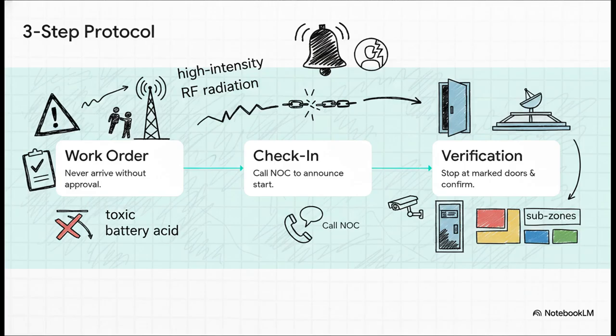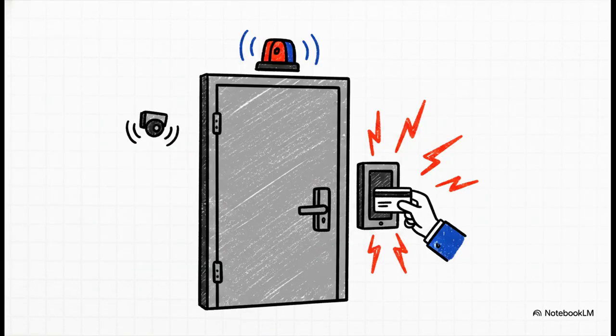First, you must have an approved work order. Second, you have got to call the NOC to check in and announce your arrival. And third, you must verify your restricted zones. Just because you have access to the front door, it doesn't mean you have clearance to enter a subroom with secure servers or step out onto a rooftop with live microwave antennas. Your badge is your key, absolutely, but it is not an all-access pass. If your badge doesn't work, contact the NOC rather than forcing entry. Remember this, a professional is patient, whereas an intruder is impulsive.